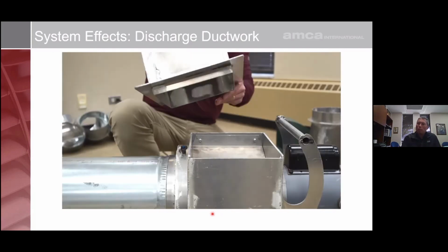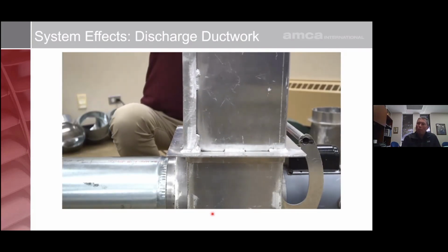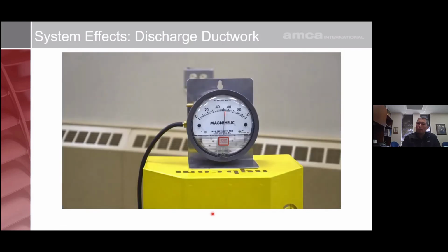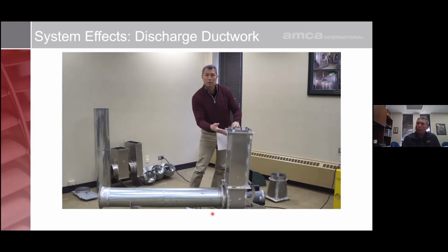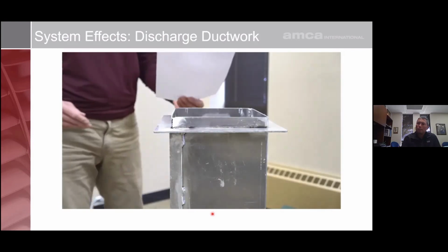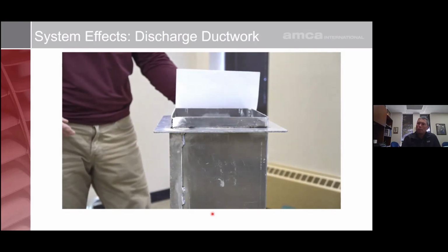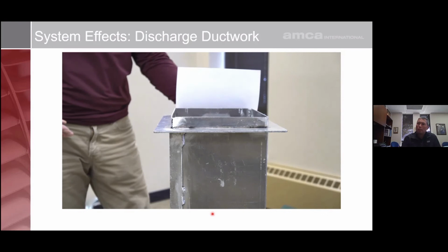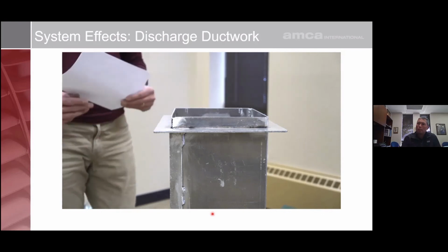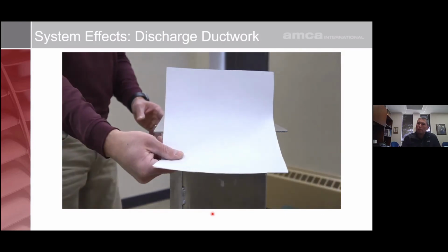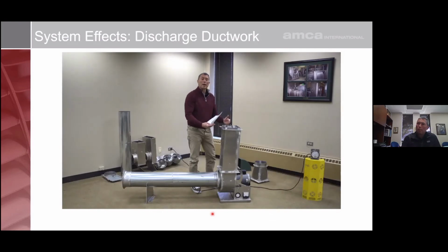Putting this ductwork on the outlet of the fan, notice that there is a change in performance when you look at the magnehelic gauge, that it's actually dramatically improved. And the reason it's improved is that the air velocity profile that has gone through this piece of ductwork has actually evened out. So if I put the same piece of paper here, notice it blows the piece of paper up. It's no longer negative pressure at this section. And if I do the same thing at the other side, it's positive pressure as well. So now we have laminar flow, and that laminar flow results in increase in performance.